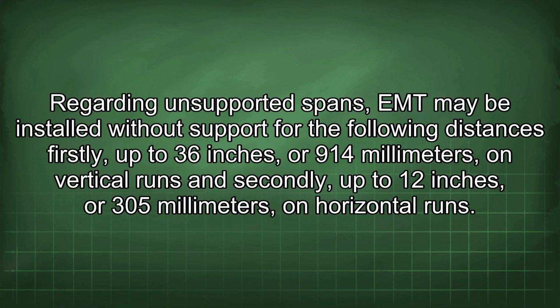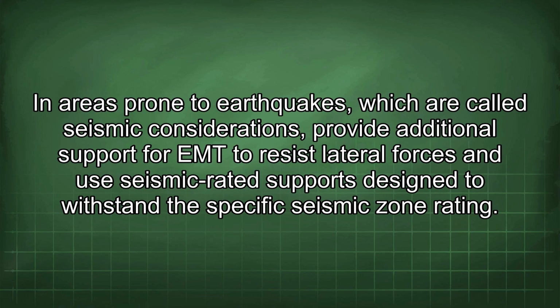Regarding unsupported spans, EMT may be installed without support for the following distances: firstly, up to 36 inches, or 914 millimeters, on vertical runs, and secondly, up to 12 inches, or 305 millimeters, on horizontal runs. In areas prone to earthquakes, which are called seismic considerations, provide additional support for EMT to resist lateral forces and use seismic rated supports designed to withstand the specific seismic zone rating.